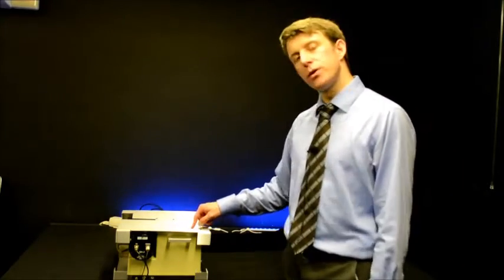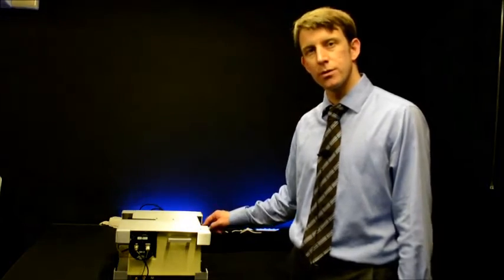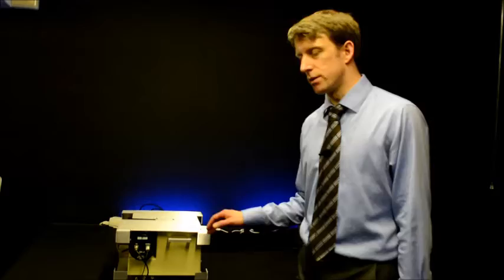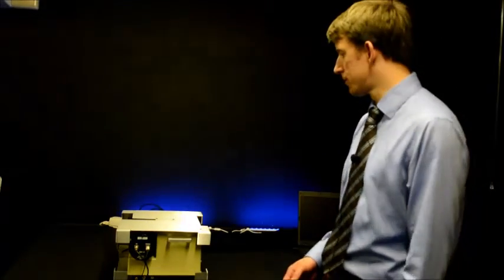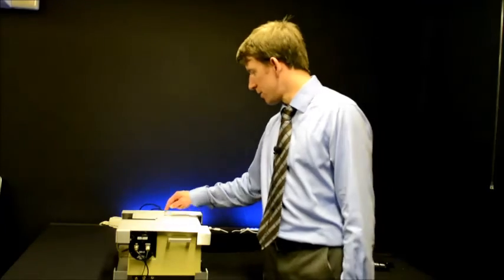The distance between the mirror and the entrance slit is 150mm, and therefore light issued from the mirror is collimated. And it's collimated onto a diffraction grating, on which diffraction obtains and interference results. Light is collected by a second spherical mirror and is transmitted through a middle unchangeable slit to the second component monochromator, in which the same process occurs.